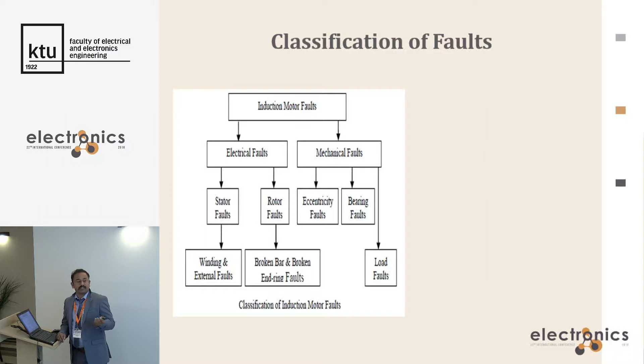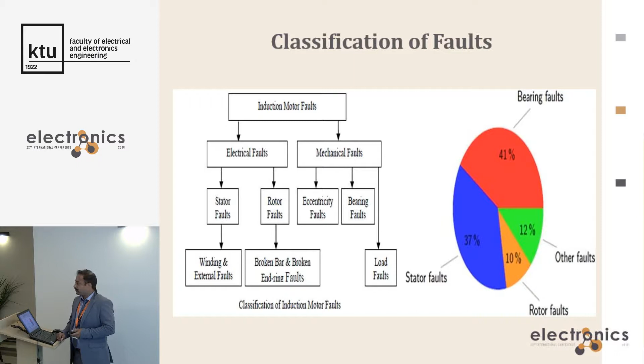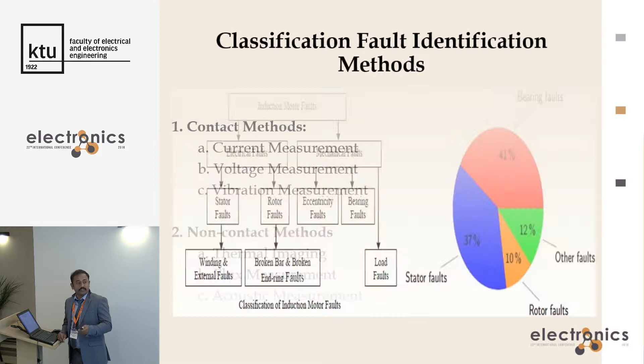And coming to the overall faults occurring in squirrel cage induction motors, rotor bar faults cause 10% of the machine failures, which is almost the minimum. The next major one is the stator faults, which is almost 37% of the overall contribution. These stator faults can be managed or reduced with a better winding as well as a better design of the stator. The remaining major cause of failure is the bearing faults, which is almost 41%, and which we are trying to address in this presentation.